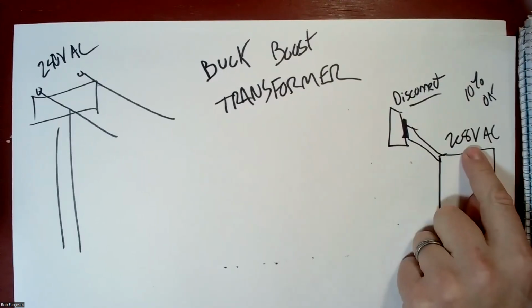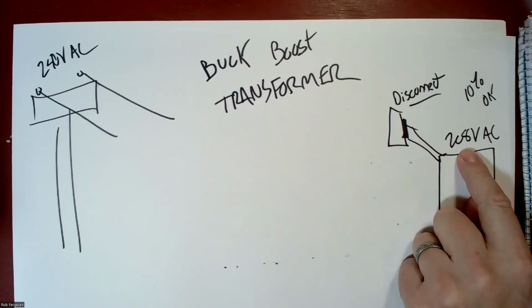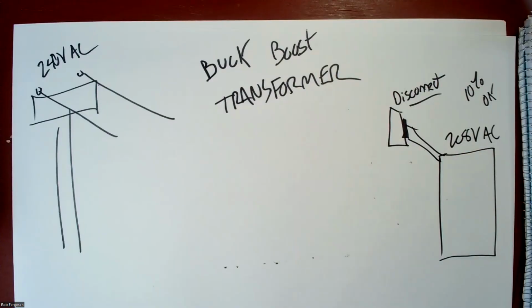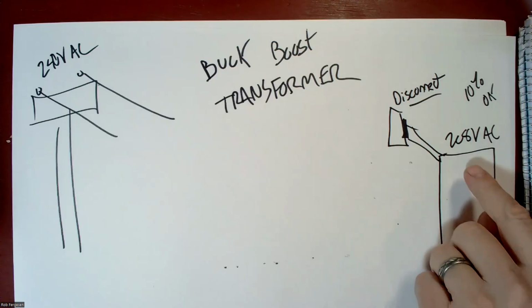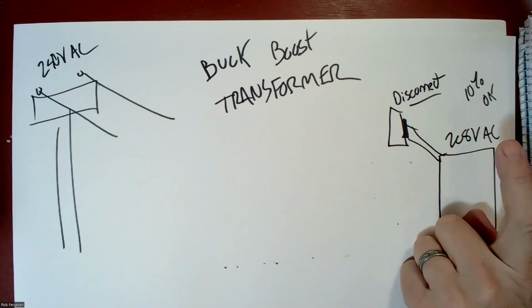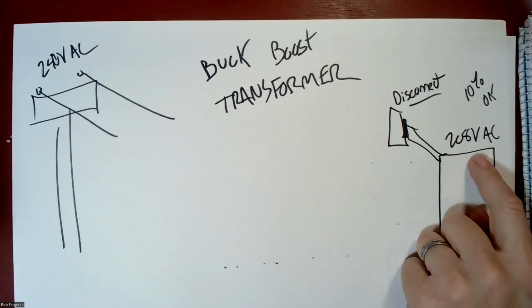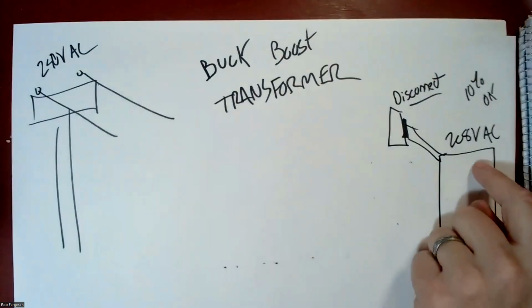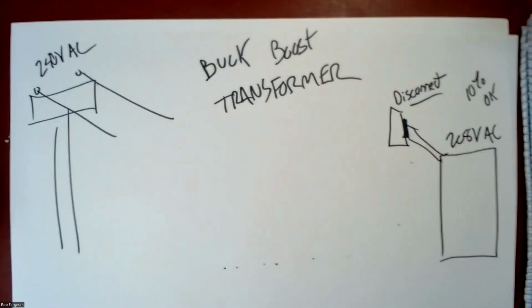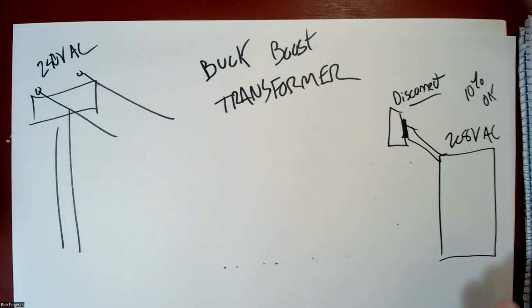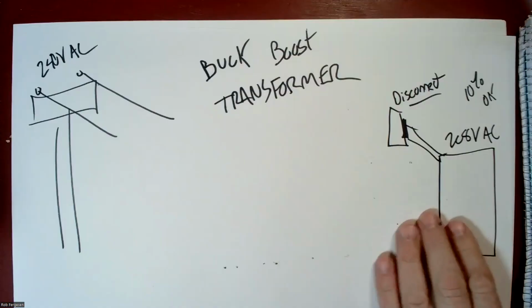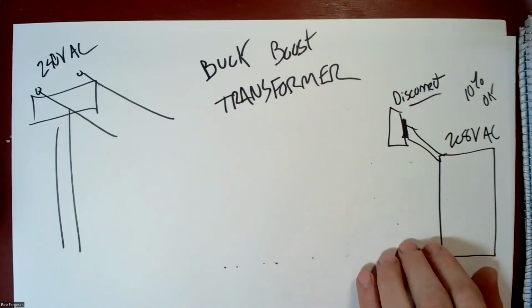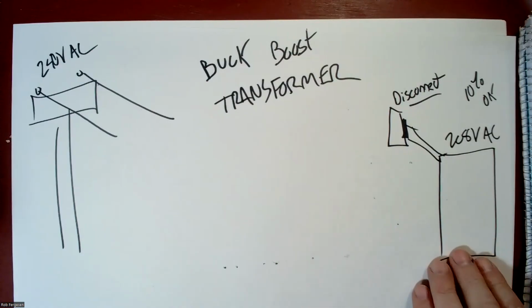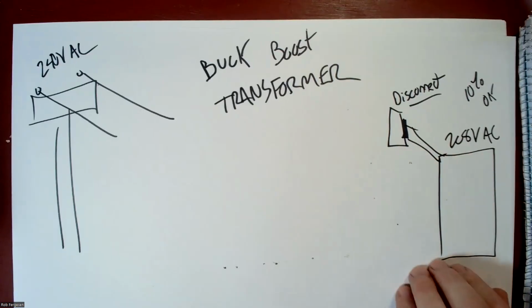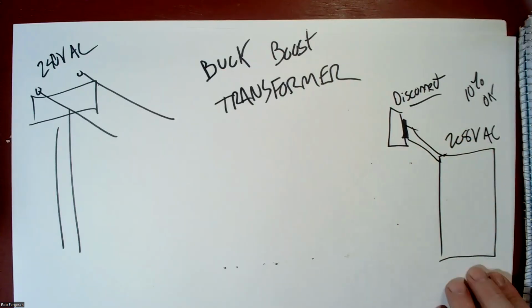But here we can see that if we add 10% to 208 volts, we're only getting up to 228 approximately, 229 to be exact. And that's not enough. It's too low for my 240 volt. I may cause problems in my device. A lot of times buck boost transformers are installed for equipment that was wired wrong to begin with, slightly low or slightly high, and you're solving weird problems with fuses blowing and equipment not working right.